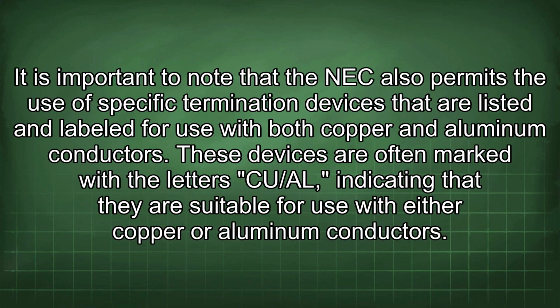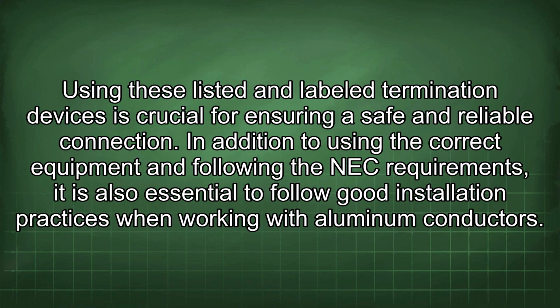It is important to note that the NEC also permits the use of specific termination devices that are listed and labeled for use with both copper and aluminum conductors. These devices are often marked with the letters CU/AL, indicating that they are suitable for use with either copper or aluminum conductors. Using these listed and labeled termination devices is crucial for ensuring a safe and reliable connection.